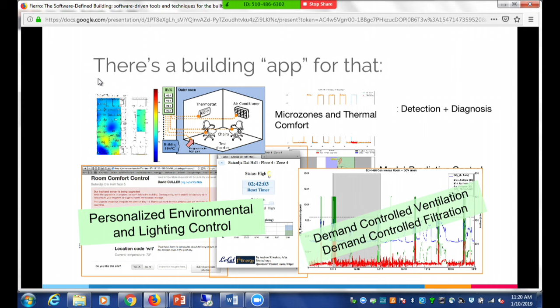There's a huge disconnect between where academia is in terms of cutting-edge algorithms and new methods, and what's actually deployed. We can look at the difference in damper position over the course of the day, and if you control for solar influx into the building, you can predict when people are going to be there, because you can measure how much the building reacts to the heat generated by the human body. But you can't just go and buy that off the shelf. There's still a disconnect between how that software gets written, how these new analytics get developed, and how they get executed on the building.